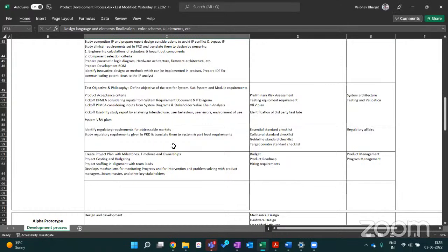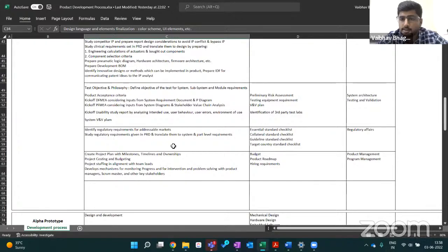So have you also done these mechanical tests, if there is some mechanical test required for a ventilator? If you are going for silicon mold, all these parameters, basically your material will change, right? So how do you overcome that issue? Okay, so definitely there are going to be some tests which are not going to get satisfied because of some prototyping method, for example the impact test or the shock and vibration test. Those we just wait for the final injection molding parts to come, but those tests won't affect the internal performance of the device. So the other trials can still continue. The final certification can only be done on the final parts which are going to be used.